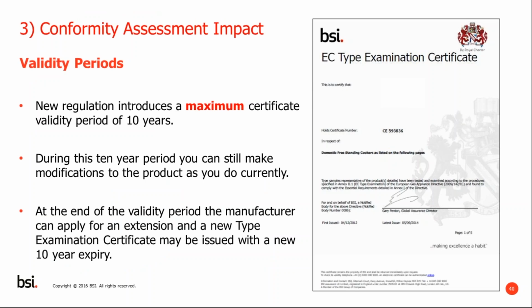There's a new requirement under the GAR on validity period. The new regulation brings in a maximum certificate validity period of 10 years. There was previously no maximum period, so this now keeps the approval of that particular appliance to a maximum of 10 years. During this 10-year period, you can still make modifications to products as manufacturers currently do, but at the end of the period, the manufacturer has to apply to the notified body again for an extension or a new type examination certificate with a new expiry of 10 years.